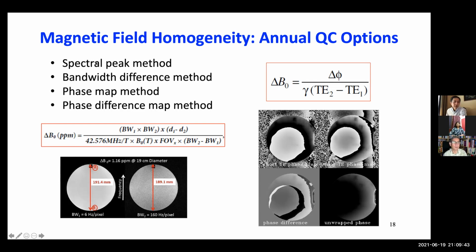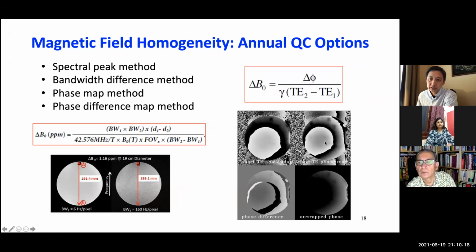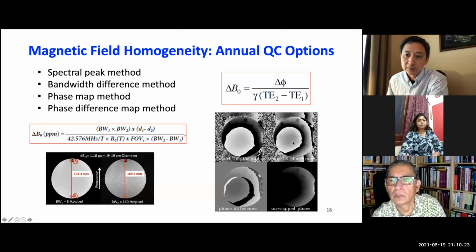Either of those 2 methods provides overall homogeneity. They cannot tell you which location has bad homogeneity. So the 3rd and 4th methods, the phase map methods, can provide information about where in the area there is bad homogeneity, because they provide a homogeneity map. The most standard method I mentioned is the phase difference map. Here is an example. We do a gradient echo image with 2 TEs, a short TE and a long TE. These are not magnitude images, but phase images. Then we can subtract the 2 phase images and get a phase difference map.